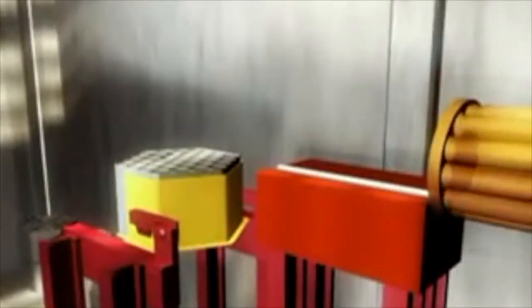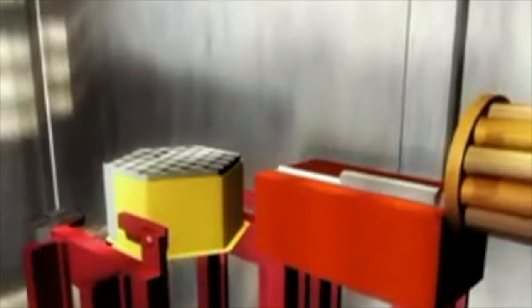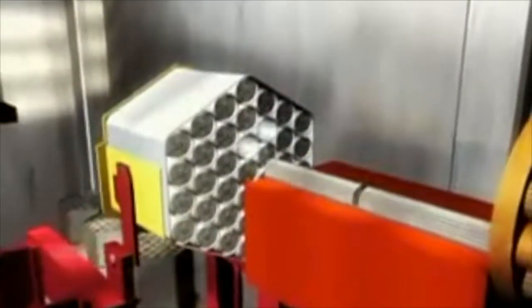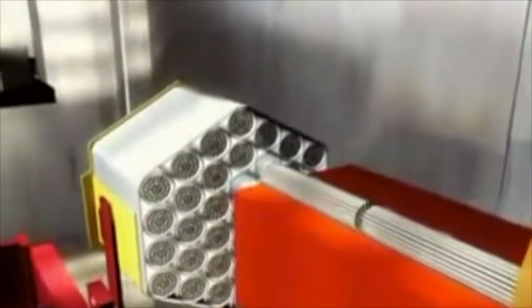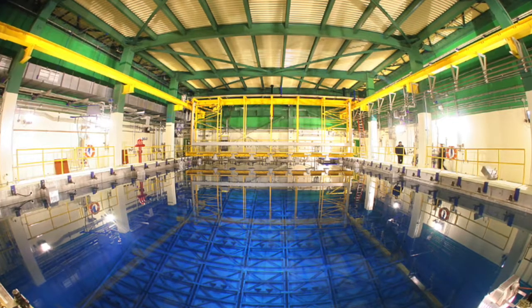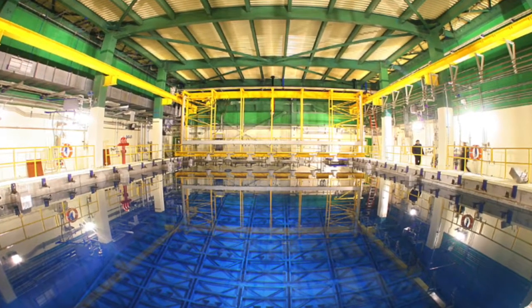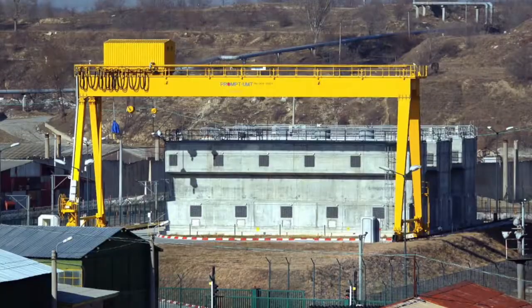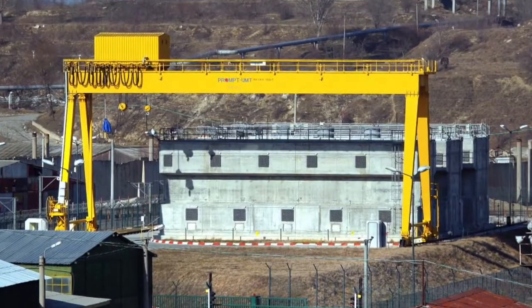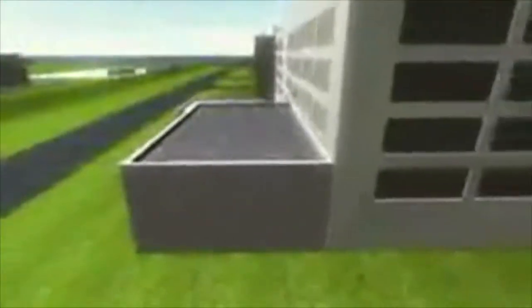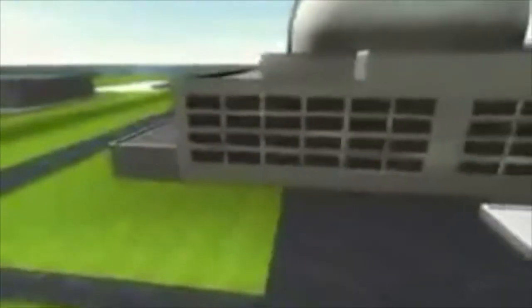The spent fuel bundles are transferred into stainless steel storage baskets. Each storage basket holds 36 bundles. Once filled, the baskets are moved underwater to the main storage bay. Typically, the spent fuel is stored here for up to six years, after which the fuel is dried and the sealed baskets are transferred to on-site dry storage. On-power fueling has been employed safely and successfully in CANDU plants that have been designed and built by AECL around the world for over 40 years.